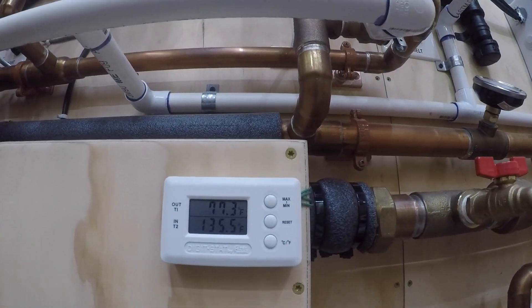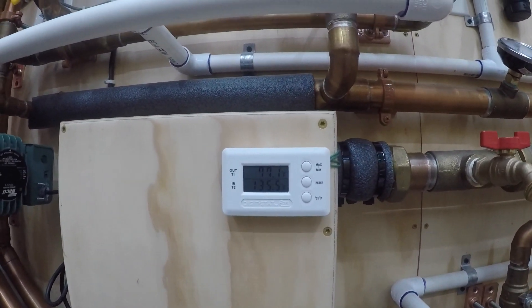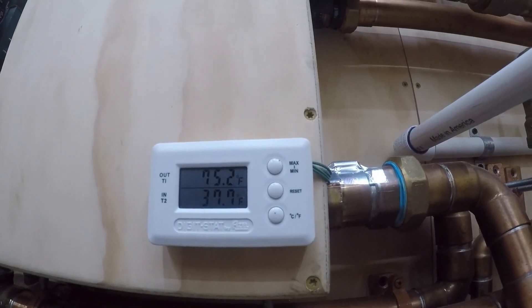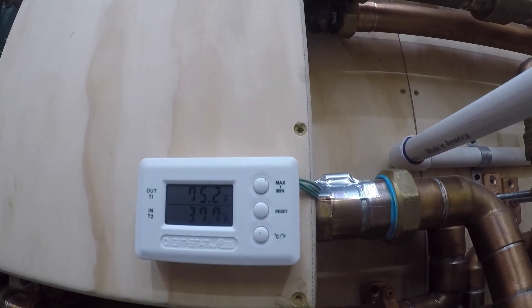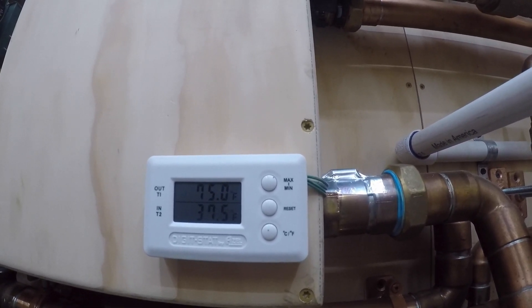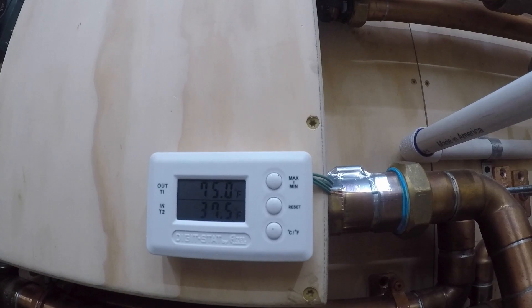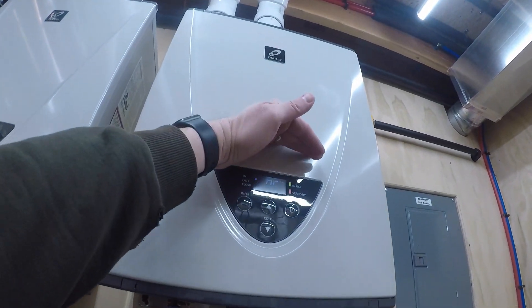What this is showing: domestic in coming in from the heaters is at 135.3 degrees, and what it's putting out to the slab zones is 77.1 degrees. Down here, coming in from the slab, it's 37.7 degrees on the glycol side, and going out on the domestic side back to the heaters this is showing 75, and up here we're showing 76.